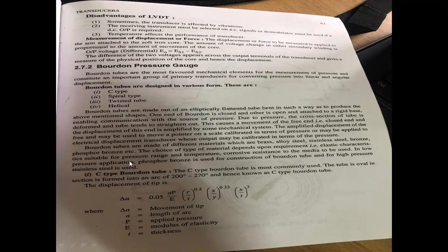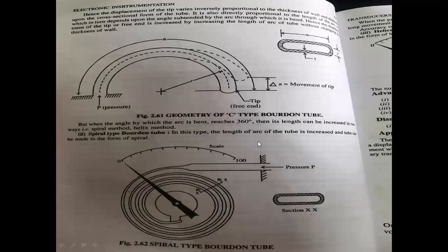For high pressure applications, stainless steel is used. The C-type Bourdon tube is the most commonly used. This tube is oval in shape and the arc spans from 200 to 270 degrees. When pressure is applied, the free tip end moves, displacing to a new position.